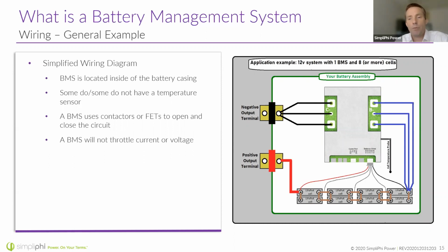For those sets that are in series, we have to keep them balanced, because as current flows through these cells in series, the current through one set of cells is limited to the current through another - they all have the same current. But if the individual cells have slightly different capacities, the cells can be out of balance, and one set could run out of current or capacity before another. So what a BMS does is constantly monitor and make sure all those cells are topped up at the end of the charging cycle. We'll get into that a little bit later. So that's what those 4 wires at the bottom are for.